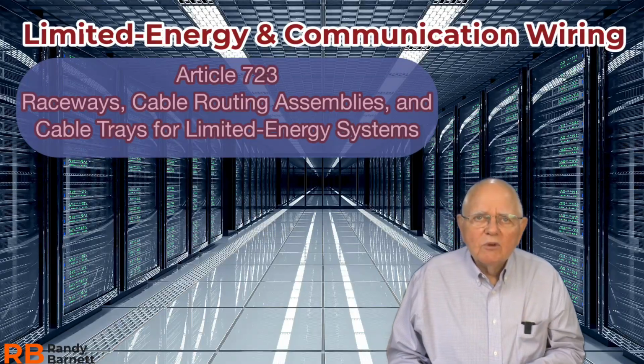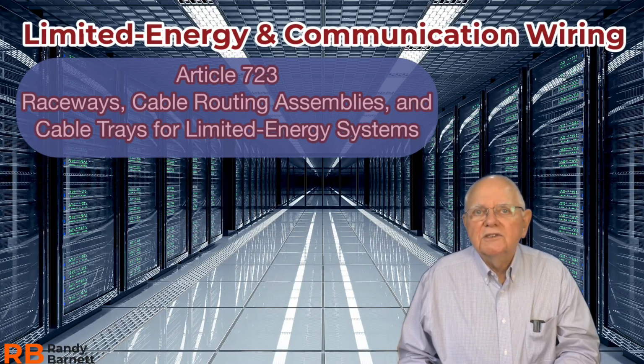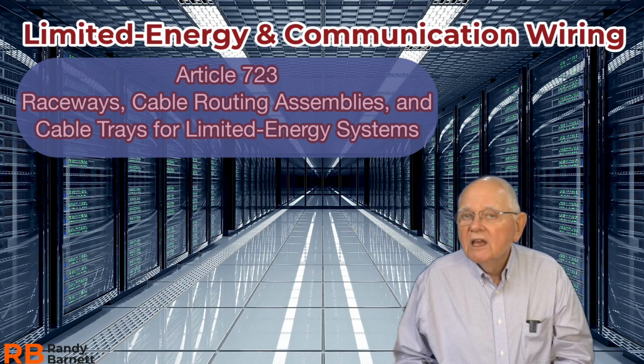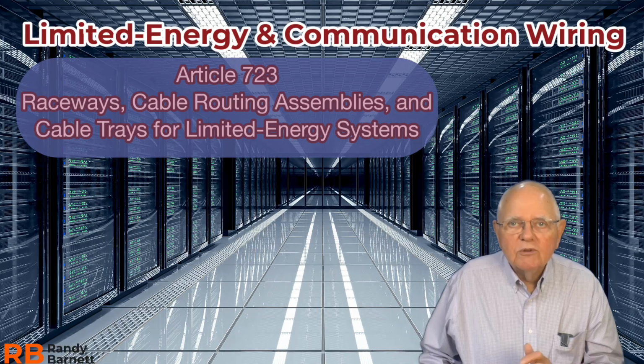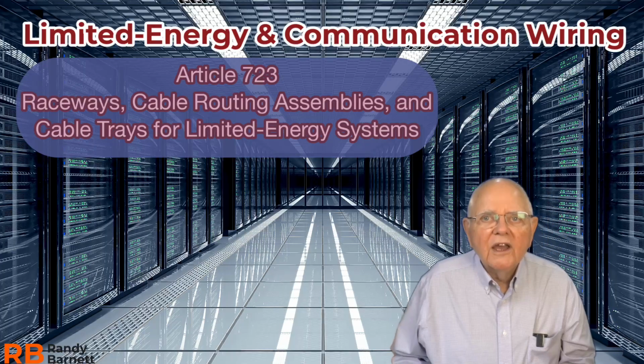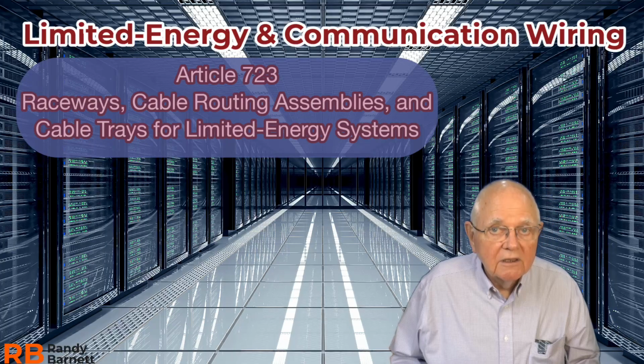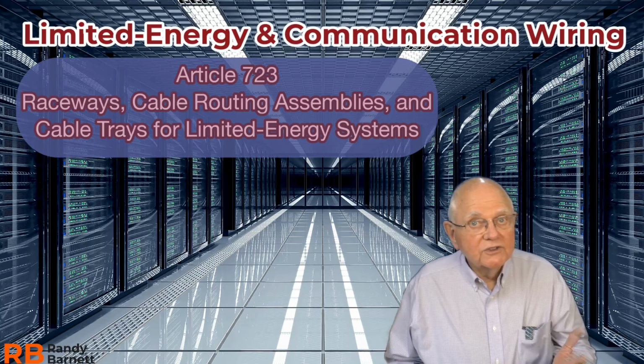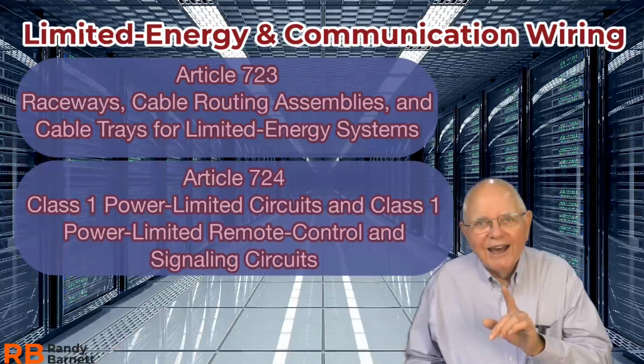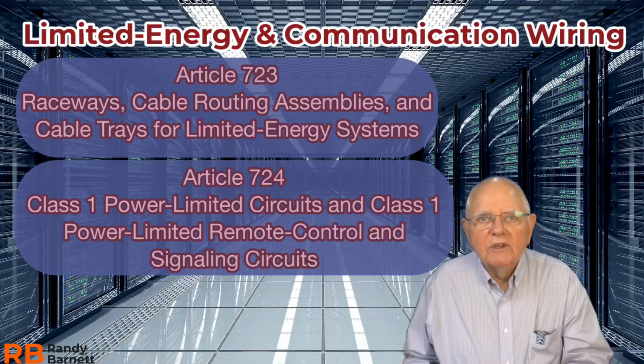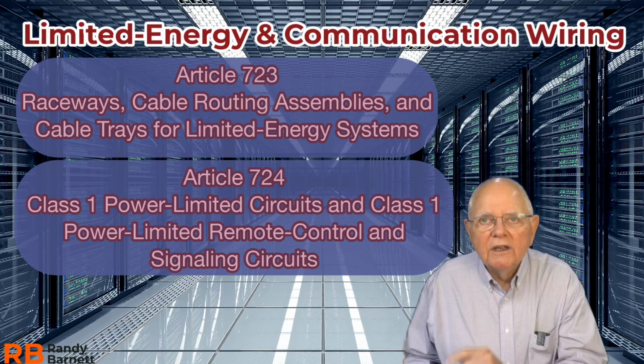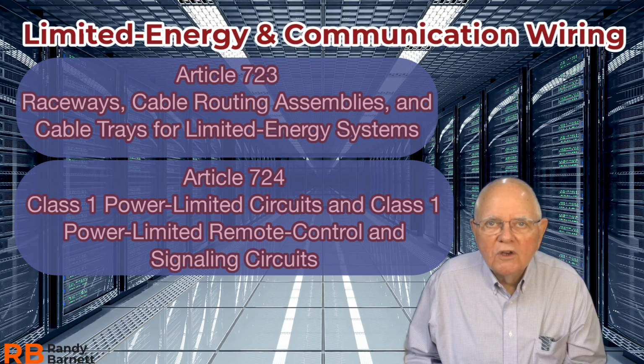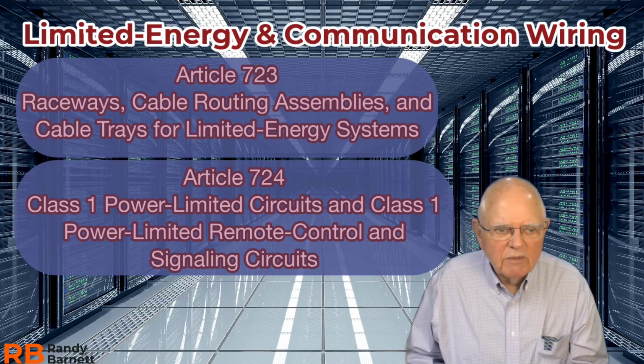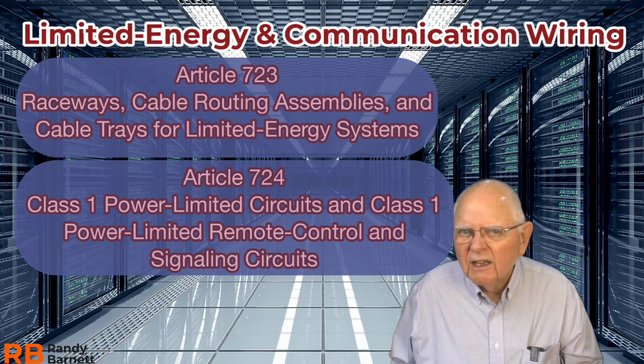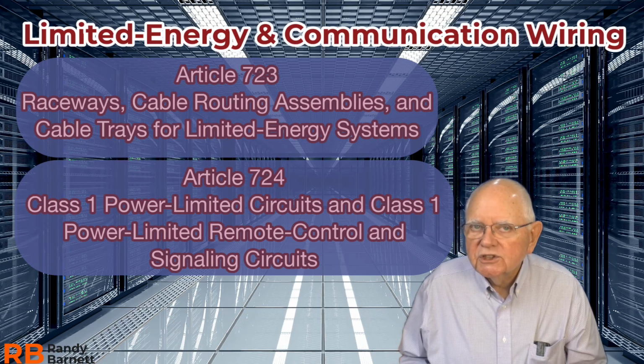Article 723, raceways, cable routing assemblies, and cable trays for limited energy systems. Once again, take a look at the tables. Tables for different applications and what type of raceway or cable routing assembly may be used. Article 724, Class 1 power limited circuits and Class 1 power limited remote control and signaling circuits. So we're talking about maybe some motor control circuits, something like that. They're not limited energy systems.